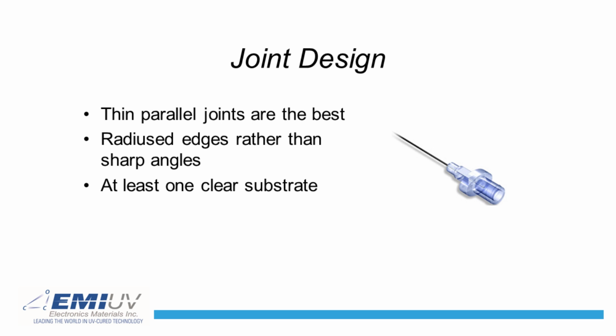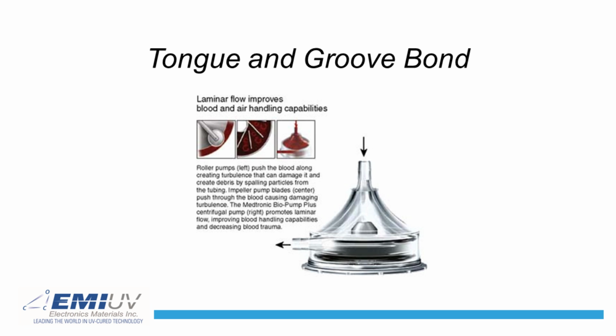Ideally, the bond thickness should be somewhere between, say, a half a thousandth to 3/1000ths in thickness. The radii and any edges should be smooth for good adhesive flow. Again, as in the picture of the needle hub assembly, one of the materials easily passes the UV energy. This kind of assembly is a great application, with both surfaces being bonded UV clear polycarbonate. The adhesives also create a good seal, which is important when handling blood product.